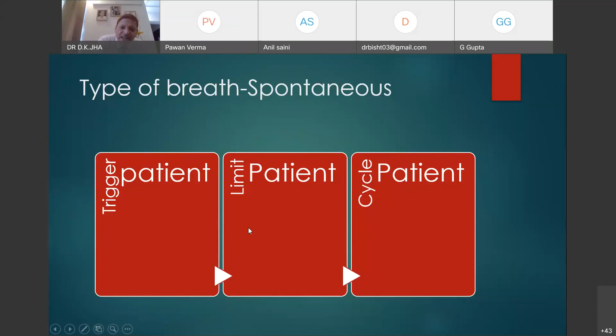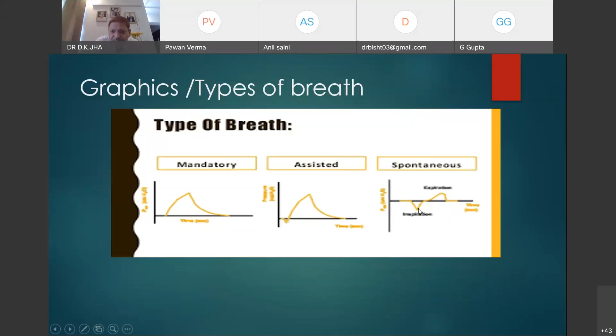Okay, so in the graphic presentation, graphics is a separate vast chapter in ventilation. I will not go into detail, I will just touch upon some important aspects of graphics of ventilation. So how will you recognize the type of breath in the graphic? See, this is mandatory breath because it is positive pressure ventilation. So this is going outside, inspiration, expiration. This is assisted. What I have said, in assisted, the patient has triggered the breath, initiated the breath. So see here, there is a negative deflection. A small negative deflection means the patient has started the breath, but the breath has been delivered by the machine. And see here, spontaneous breath. This is a negative pressure ventilation. This is the deflection, inspiration is inward, and then expiration is this.